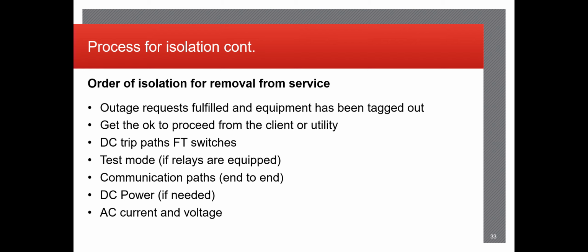Your first thing you want to isolate from the relay is the trip paths. The reason you do this first is because the trip paths are all outputs from the relays, meaning the relay won't see anything if you take away its trip path. And the reason you take these out first as well is because if you were to take out any of the currents or inputs that are going into the relay, it may think something's wrong and will trip that equipment associated with the trip path. So you take those out first. Test mode as well, any communication paths, DC power to the relay if need be, and then your last leg is going to be your current and voltage sources.